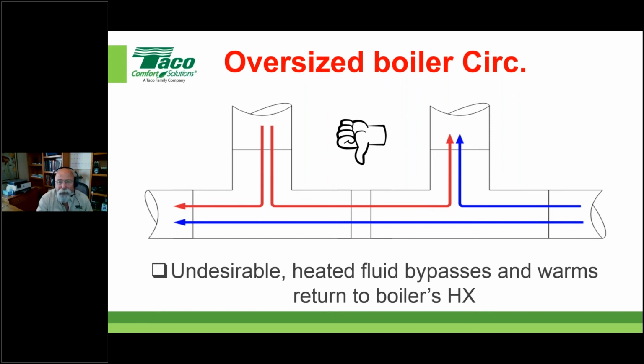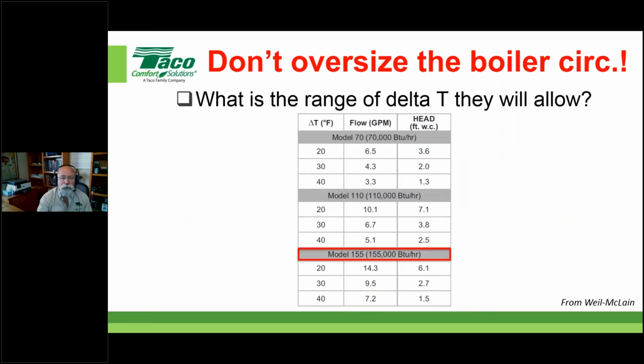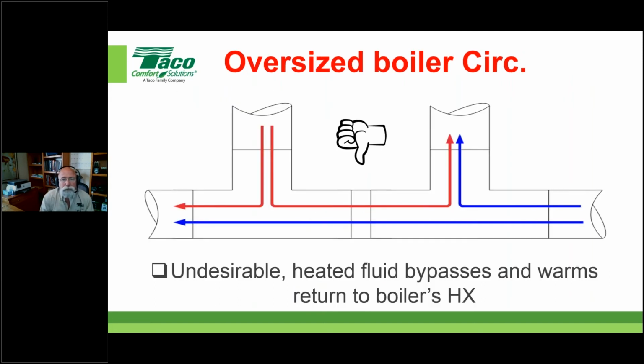Did have one other question about closely spaced tees. What does the up to 12-inch max refer to in 4 pipe diameters up to 12 inches max? 3-inch pipe. How many people are doing 3-inch pipe on this webinar right now? On a regular basis, your boilers have secondary headers that are 3-inch. That would be the 12 inches, right? 4 pipe diameters times 3 inches equals 12 inches.